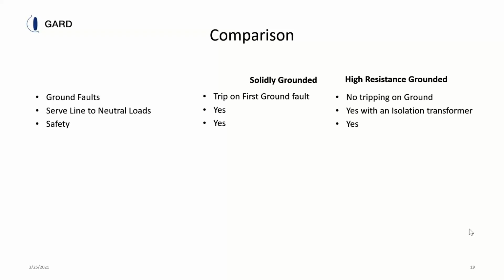So when you have a resistance grounded system and you use surge protective devices that are designed for solidly grounded systems, the two unfaulted phases elevate above ground, and the grounded phase and ground are at the same potential. So if you had a 480 volt system, the 480 volt unfaulted phases, say A and C phase, are at 480 volts with respect to ground. If your surge protective device is designed to trigger at 400 volts, you haven't done anybody any favors by using a surge protective device which is employed for a solidly grounded system for use on a resistance grounded system.